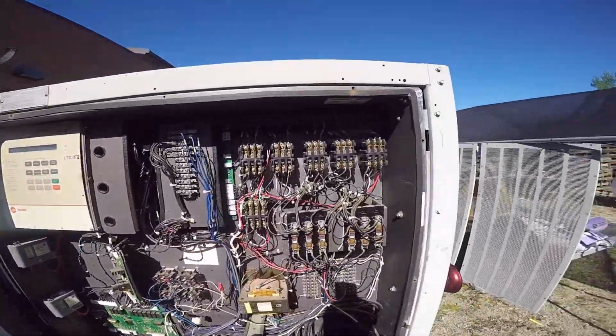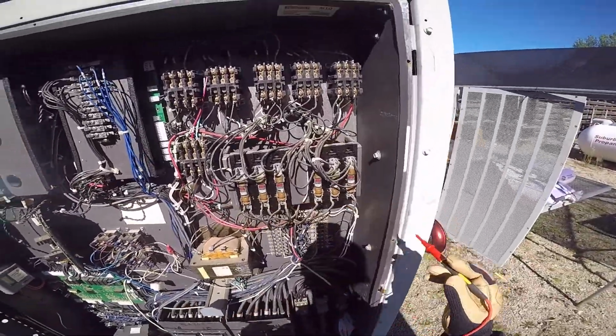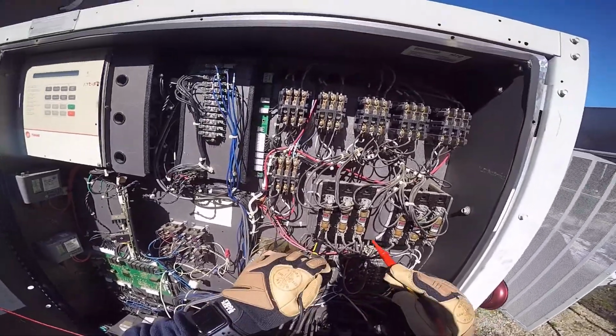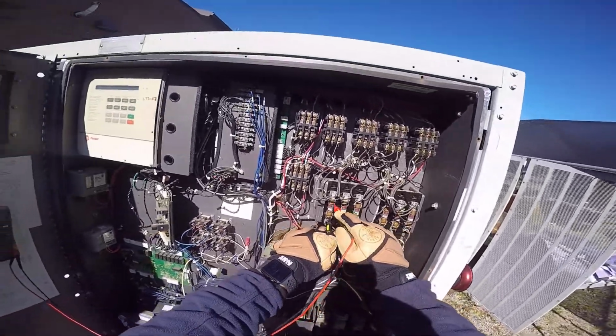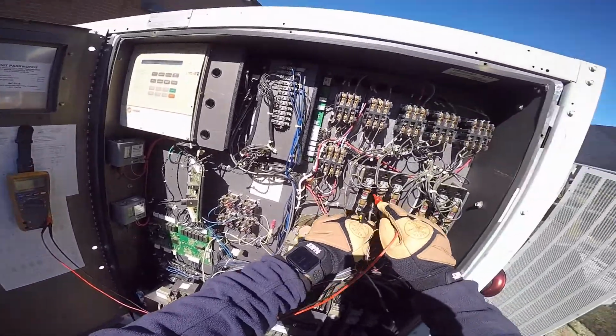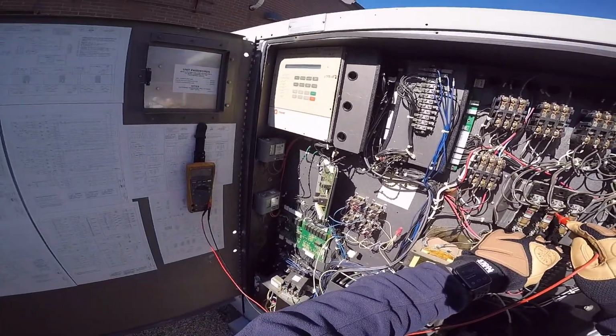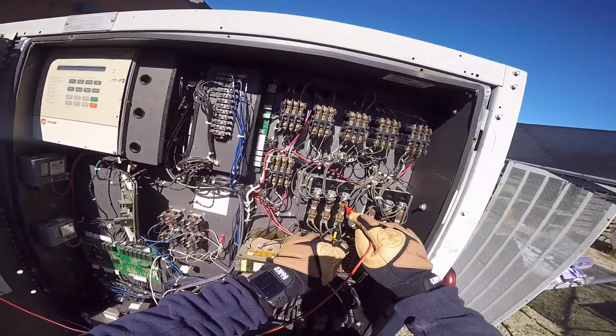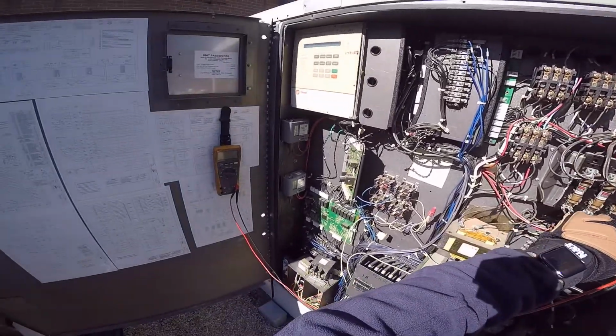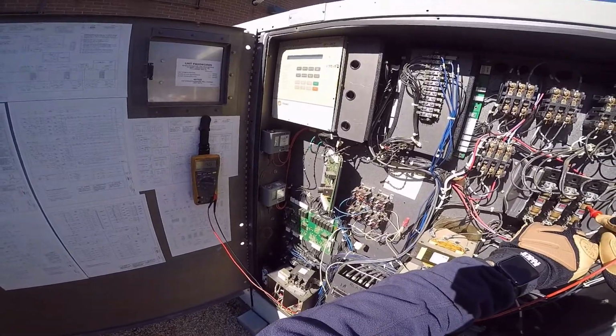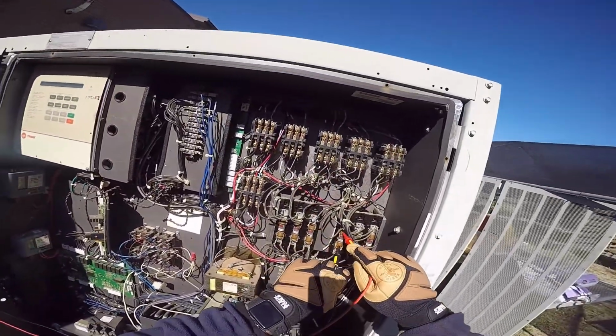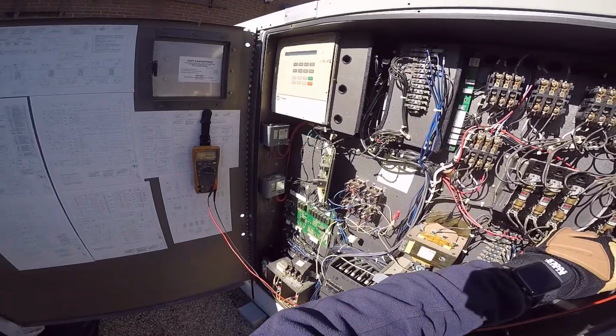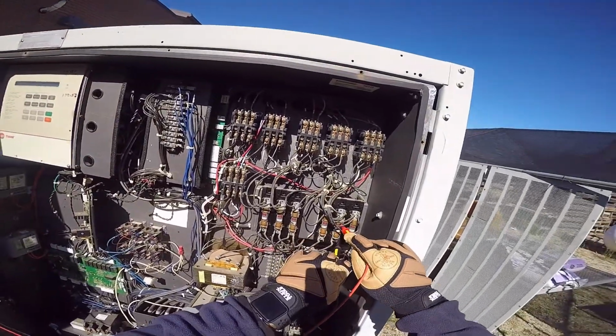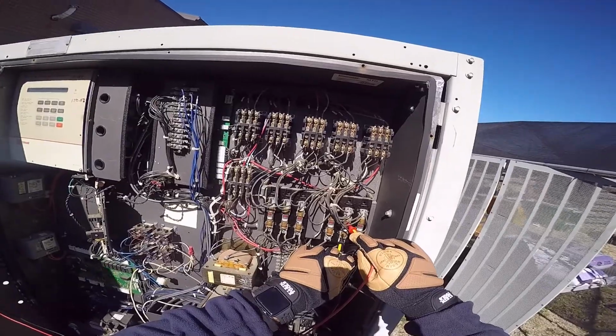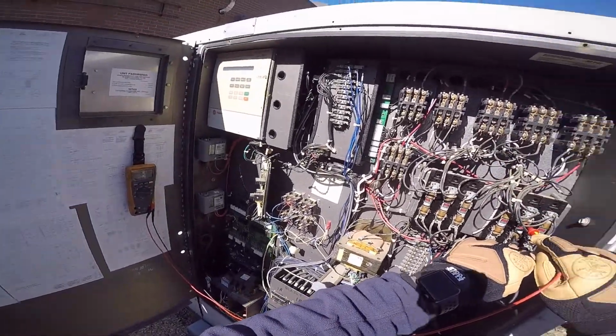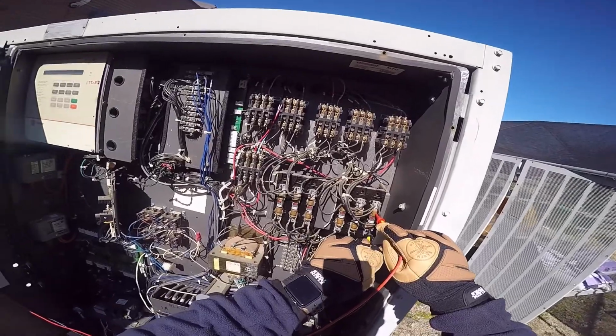The next thing we want to do is check our fuses, right here. I go from the top to the bottom, looking for 0. I got 0, 0, I got 0, I'm in millivolts. Millivolts is 0 - when I'm showing 5.2 millivolts AC, that's 0. 8 millivolts, that's 0. What I'm looking for is 1 volt or higher. If I get 1 volt or higher drop through this fuse, it's gone.